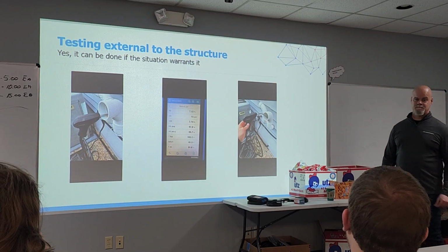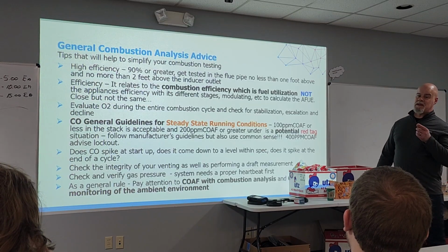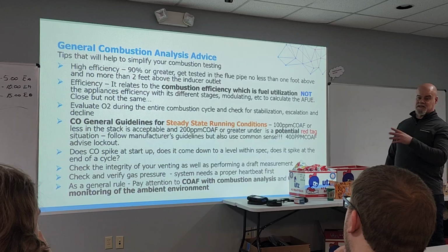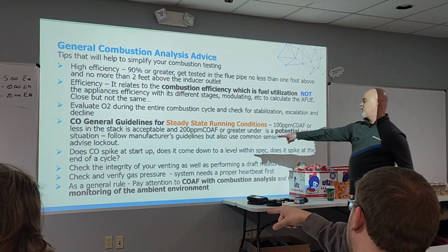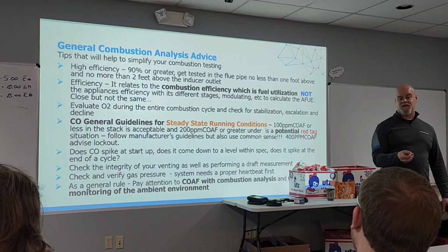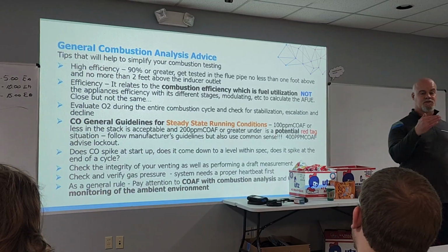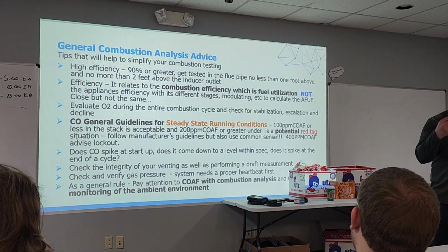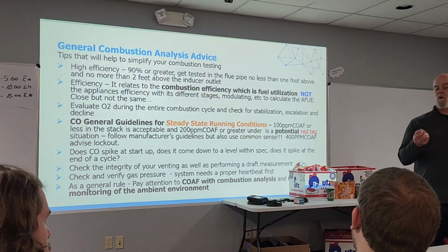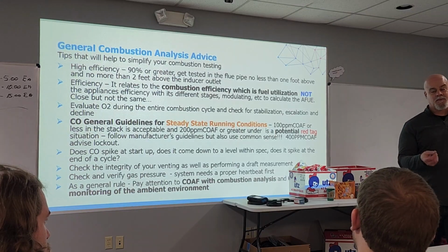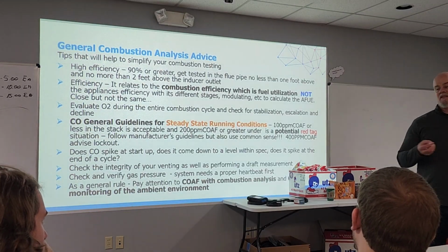Should it have a spike or no? Spike meaning at which time? Steady state, which one? So, over here, for example. It can. Every system is different: fuel delivery is different, the cleanliness of a system is different, burners are aligned differently, the quality of a flame can be different. The spuds could be, something could be going on with those. There's all kinds of things that feed into this.